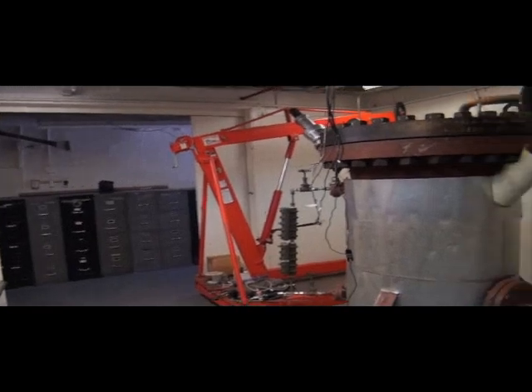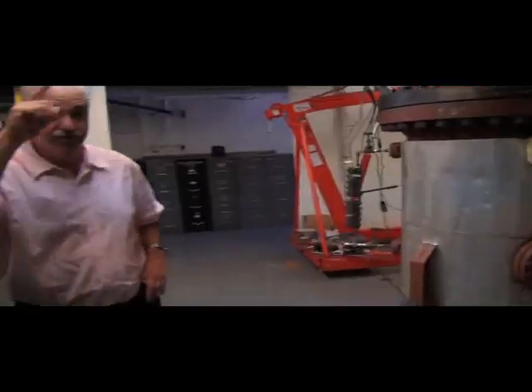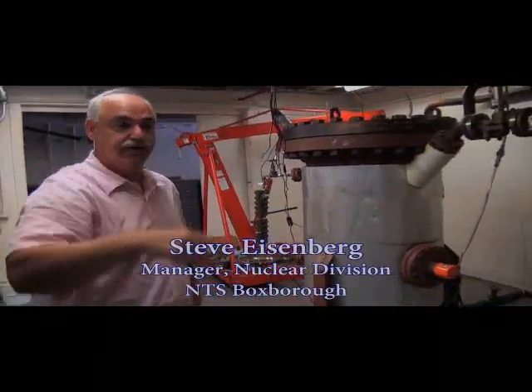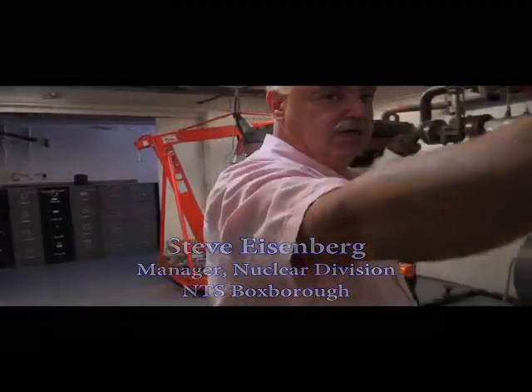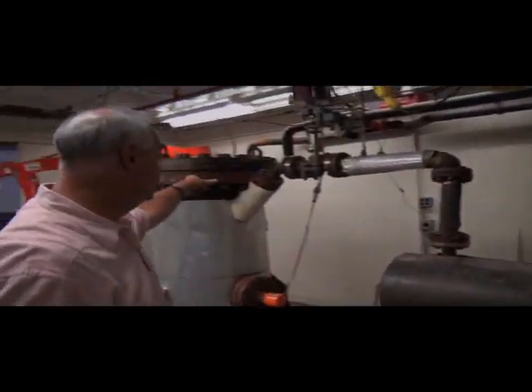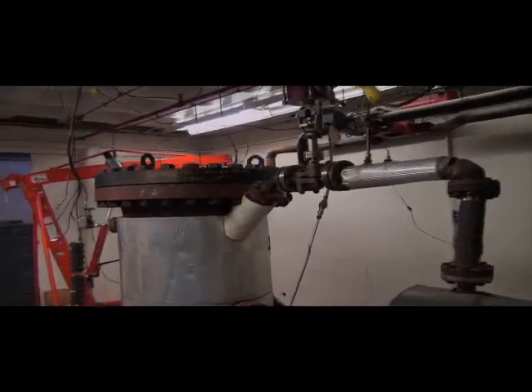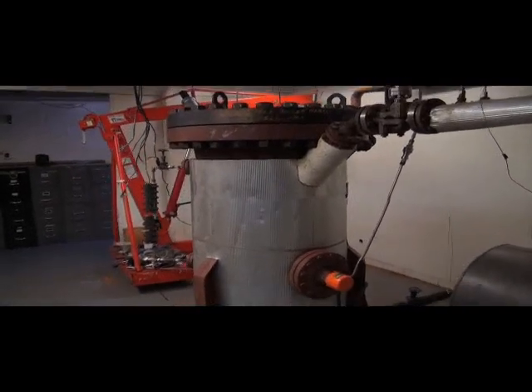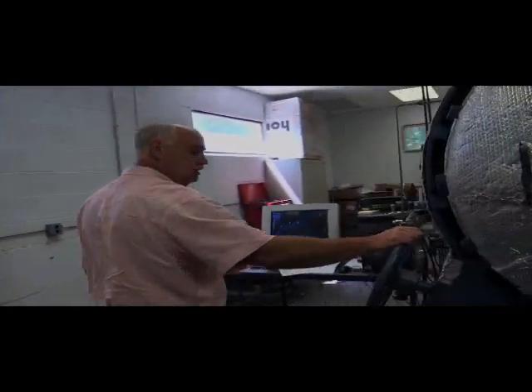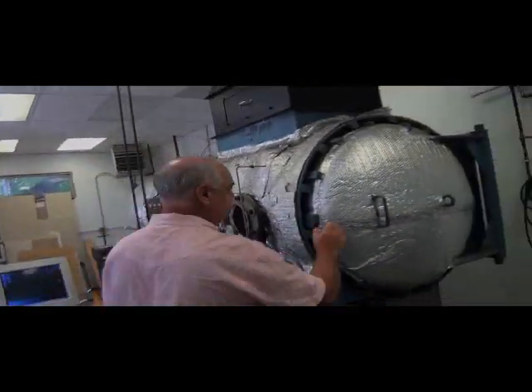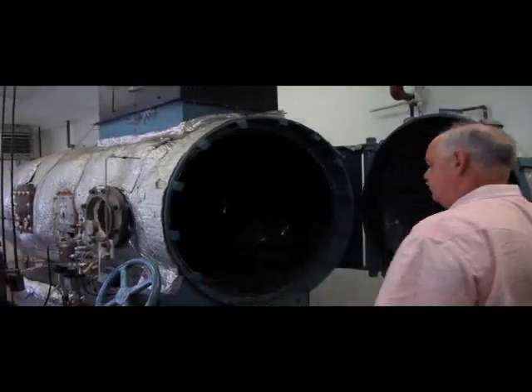This is our small test chamber. So the way the system works is we generate saturated steam in the boiler, runs through the superheater, comes out, runs through this other superheater, and we operate the valve and inject the superheated steam into the test chamber. This is our explosive atmosphere chamber. So this would be used for testing to MIL-STD 810 or to FAA DO-160.